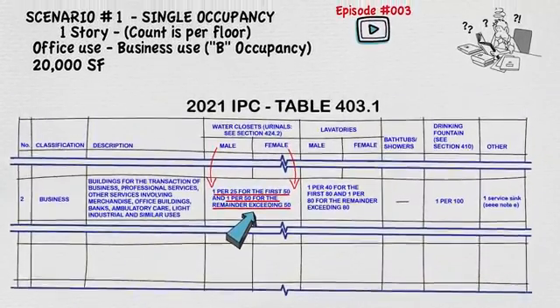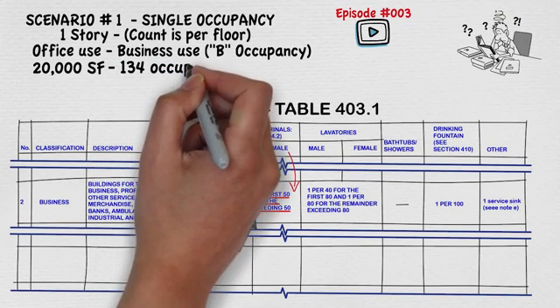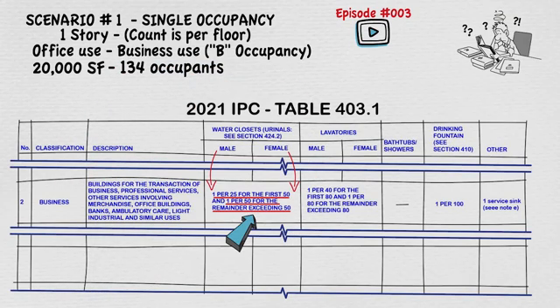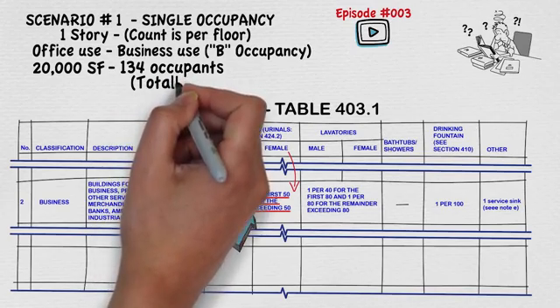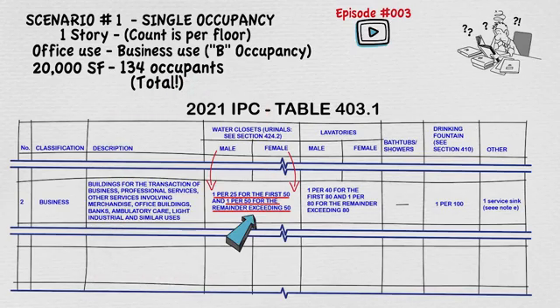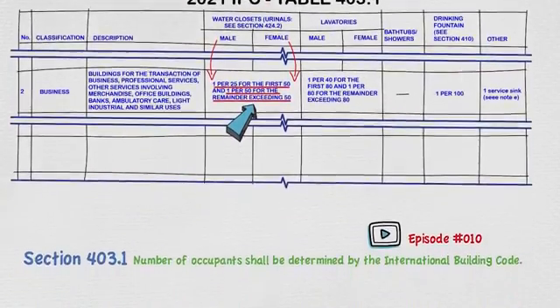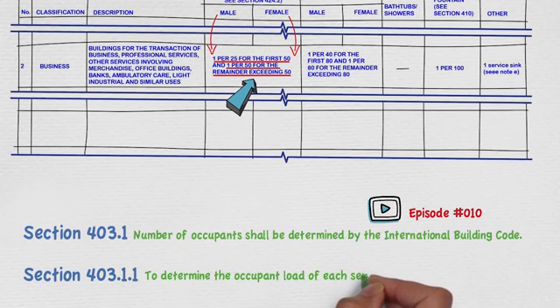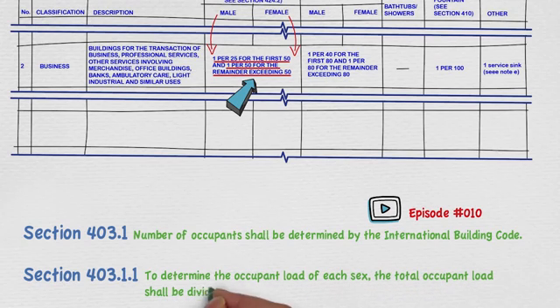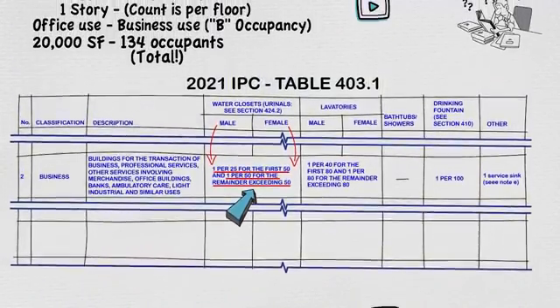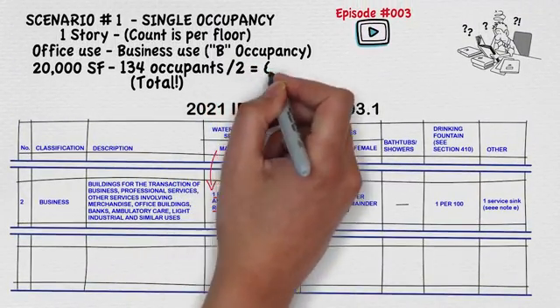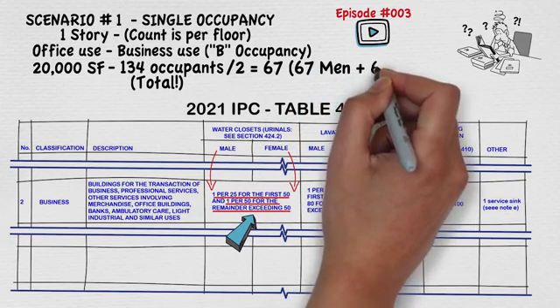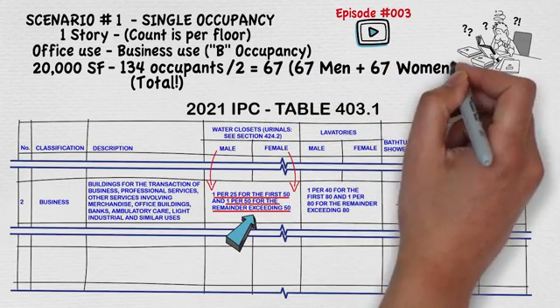For now, let's assume that we have 134 occupants. These 134 occupants are total — meaning total men and women combined. International Plumbing Code section 403.1.1 states that to determine the occupant load of each sex, the total occupant load shall be divided in half. Therefore, we divide 134 by 2, which equals 67 — 67 men and 67 women.